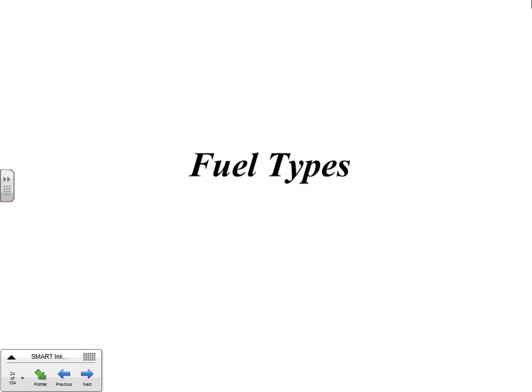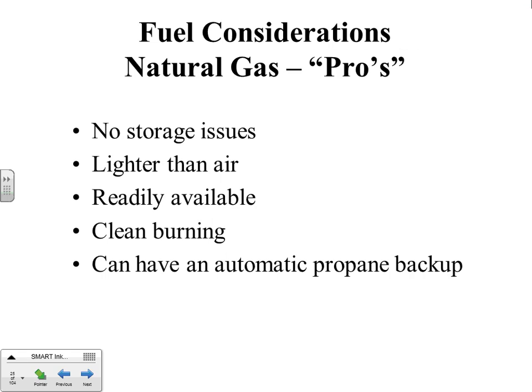Fuel types. This is where it gets a little interesting. Fuel considerations. When you design a generator set, these are some of the things you might want to be thinking about. A natural gas generator, it's a consideration. The pros in this particular fuel is you don't have any storage issues. It's city supplied, it's always available, so that's a plus. It's also lighter than air. If there's ever a leak, it's going to go up. It's readily available. It's clean burning, and it can have an automatic propane backup.